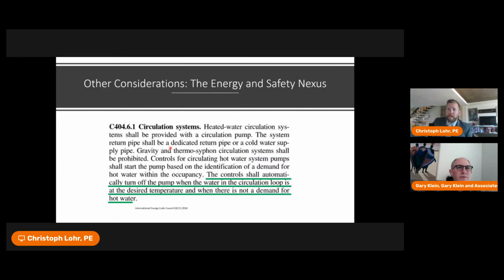When you look at some of the energy codes, actually the latest energy code in 2018, they added a requirement that the controls shall automatically turn off a pump when the water in the circulation loop is at the desired temperature and when there's no demand for hot water. In many cases, this was a requirement that was added due to bad design. And really, there's a lot of issues with this in terms of promoting the potential growth of Legionella in hot water return systems.